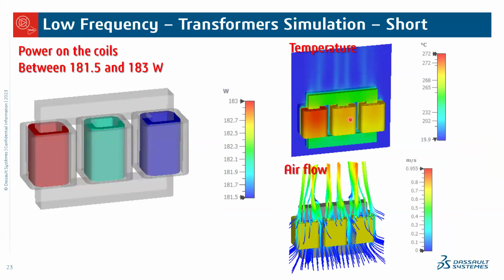This is something you can see here. What I've done is coupled the losses calculated in the electromagnetic simulation to the thermal solver, and I was able to calculate the temperature increase after 3 seconds, because this is what the standards want us to do. If you want to test the strength of your transformer against temperature, you have to inject this high current, or do the short circuit simulation for 3 seconds. And you see here, I have a temperature that rises up to 272, which is quite high.